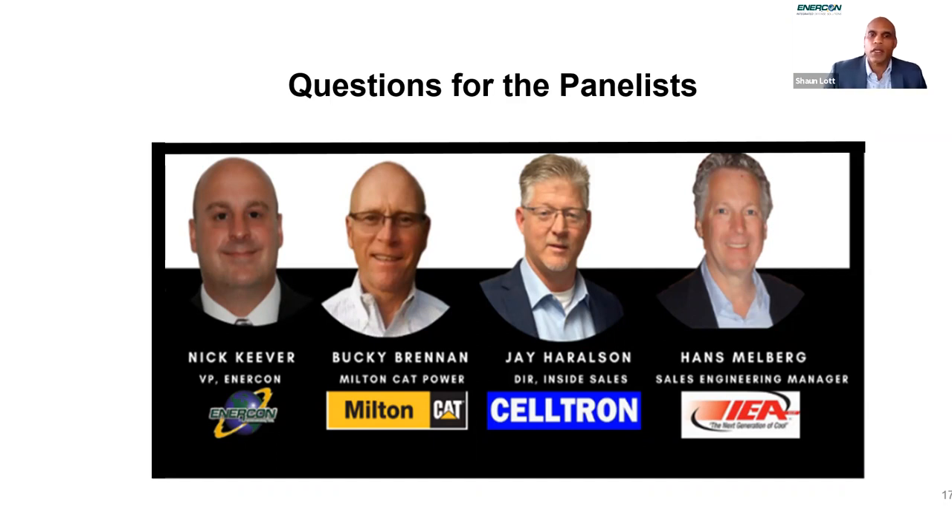We have a question on designing tactical power systems for Nick. What is the most common issue you run into based on your experience? Weight is a big one — warfighters are restricted on the equipment they can tow and transport. The prime mover specification typically comes in first, which limits your design. You do your genset selection as Mr. Brennan described, you've got your heart of the power package, and then the prime mover dictates how much weight and size you can have. That's the first limiting factor from a design standpoint when evaluating how to approach the custom solution.